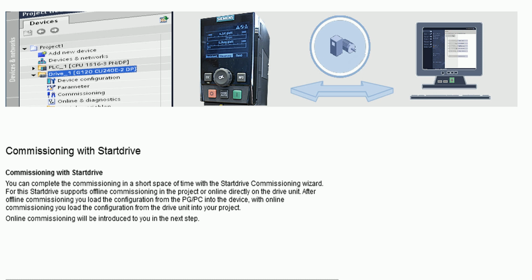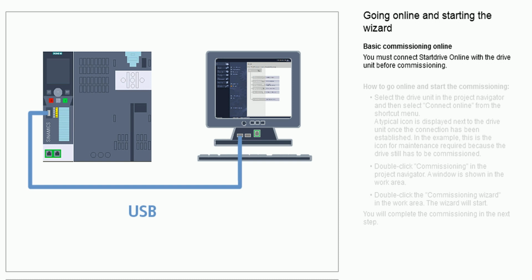Commissioning with Startdrive. You can complete the commissioning in a short space of time with the Startdrive commissioning wizard. For this, Startdrive supports offline commissioning in the project or online directly on the drive unit. After offline commissioning, you load the configuration from the PG-PC into the device. With online commissioning, you load the configuration from the drive unit into your project. Online commissioning will be introduced to you in the next step. Basic commissioning online. You must connect Startdrive online with the drive unit before commissioning.